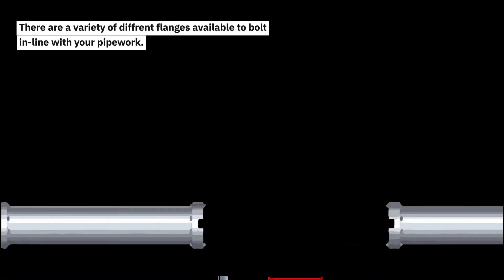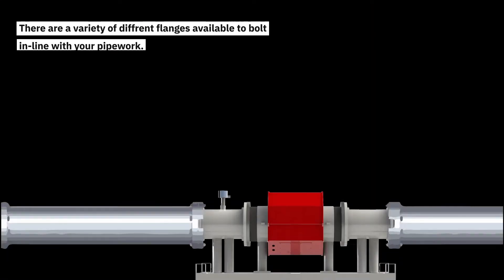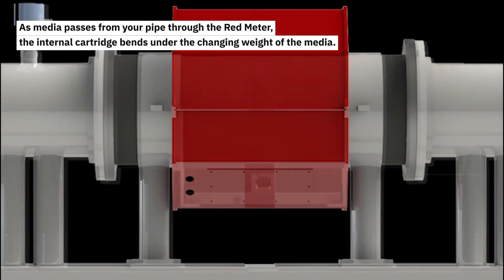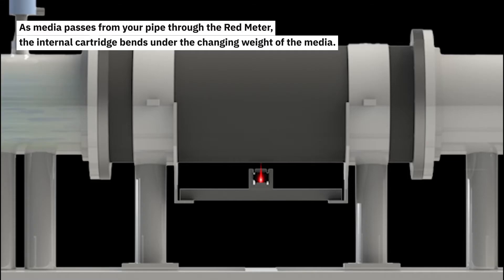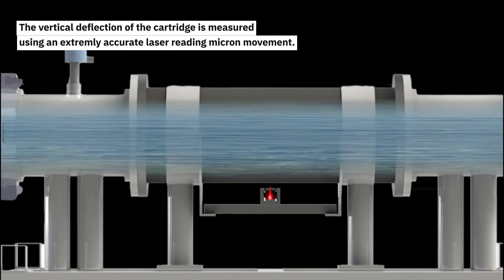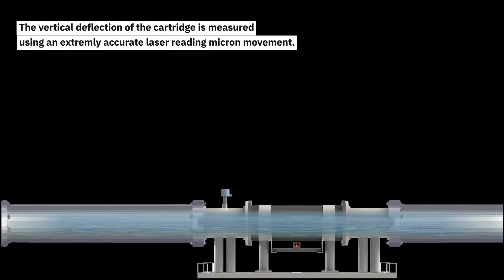There are a variety of different flanges available to bolt in line with your pipework. As media passes from your pipe through the Red Meter, the internal cartridge bends under the changing weight of the media. The vertical deflection of the cartridge is measured using an extremely accurate laser reading micron movement.